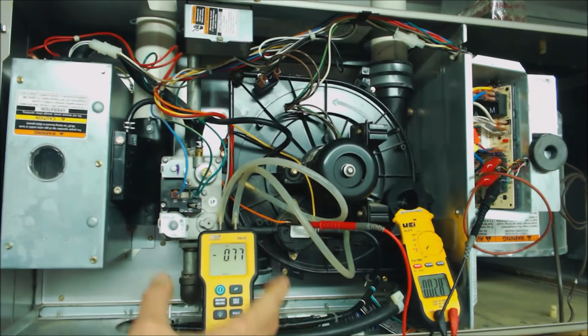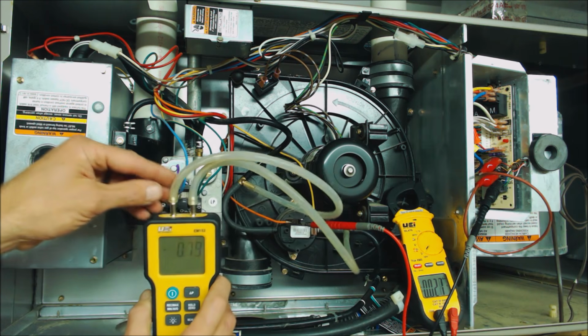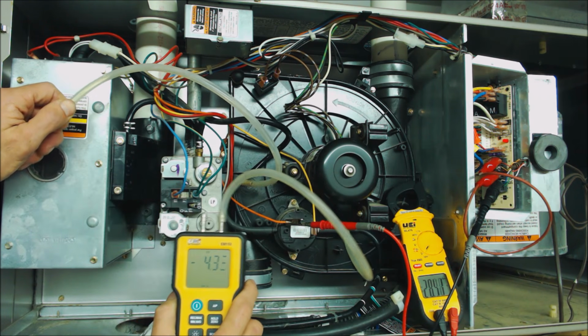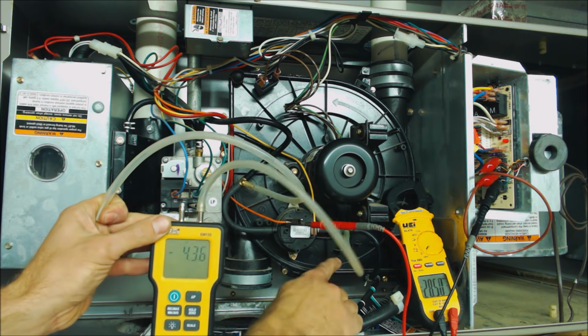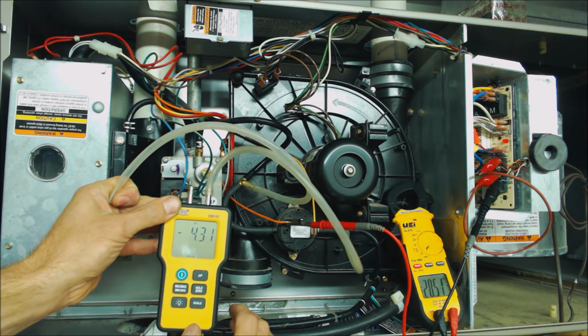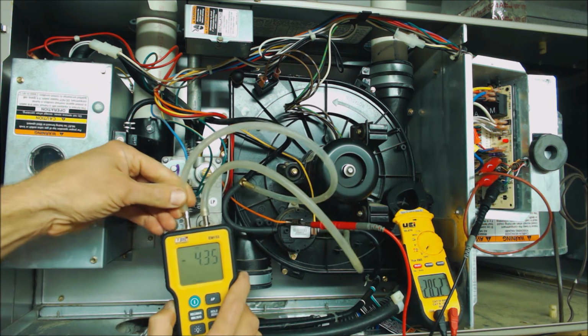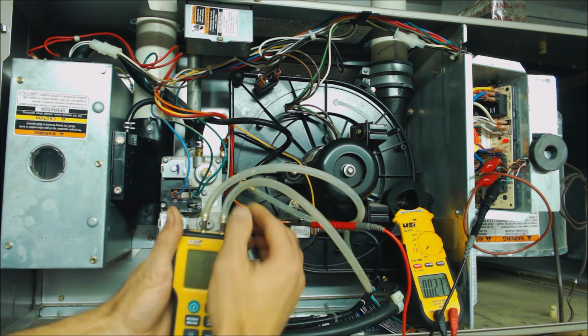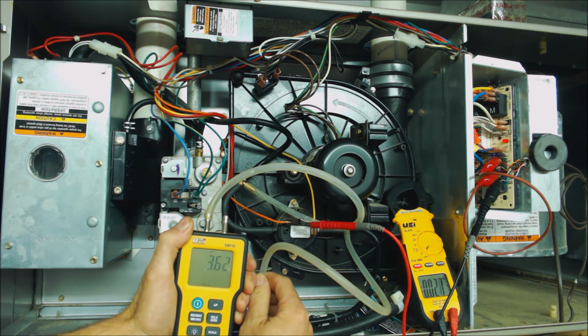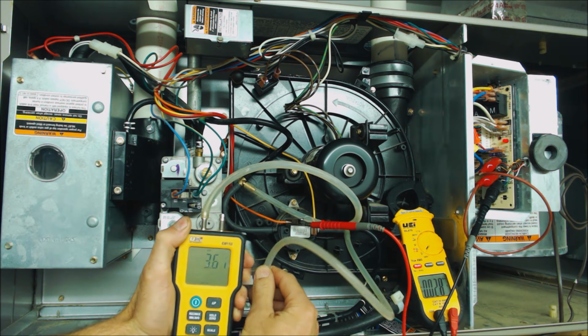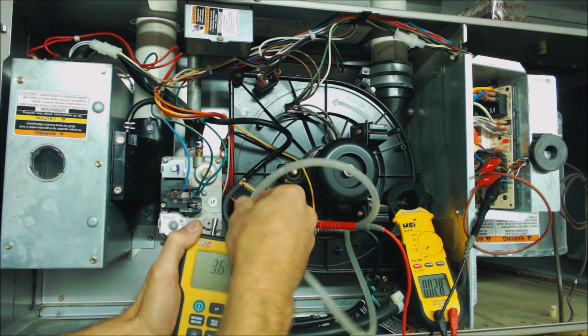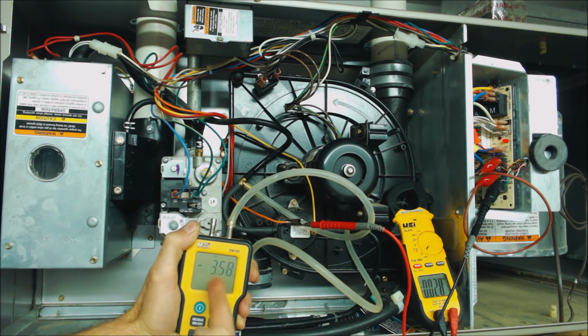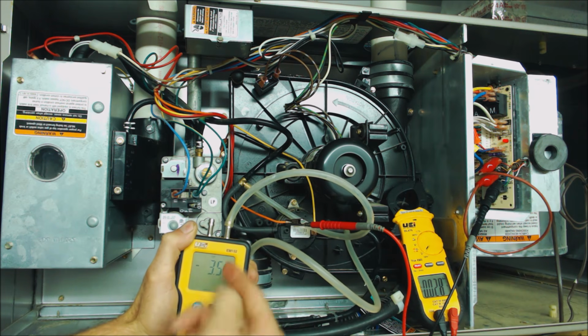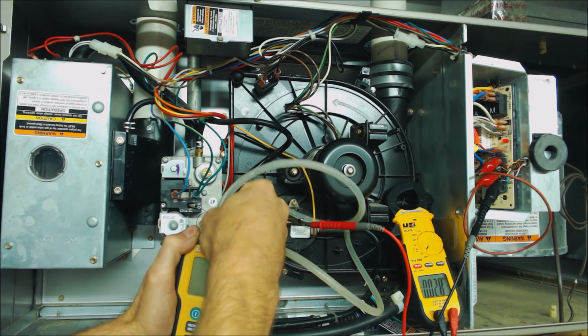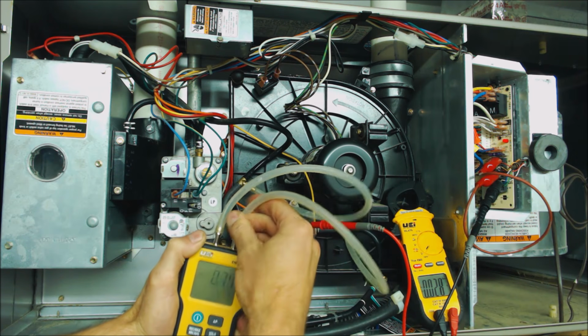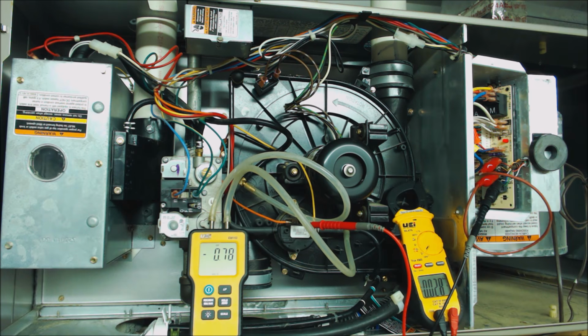So just to show you what's actually happening, I'm going to go ahead and disconnect one of these at a time. Right now we're reading the negative pressure from the inducer motor housing, which is going to be higher. So we're reading negative 4.3. Now with this other tap, we're going to read it. It's going to read positive, but it's not really a positive reading. You see it says 3.6. Just to show you, if you put it on that, it reads negative 3.6, and that's what it actually is. It's negative 3.6. So that's why the differential between the two is negative 0.78.